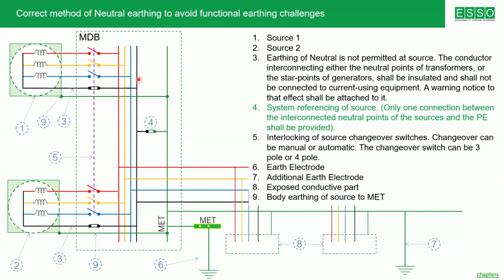Now, the advantage of this particular method of earthing, which has also been included in IS 3043 for probably 20-30 years, is that there is no reference missing of the neutral during changeover. As a result, electronic equipment malfunctioning can be avoided. Number 2, you need not make non-standard electrical earthing. So the best alternative is, at the changeover system, you make the changeover and the neutral earthing of the entire electrical installation in this particular fashion.